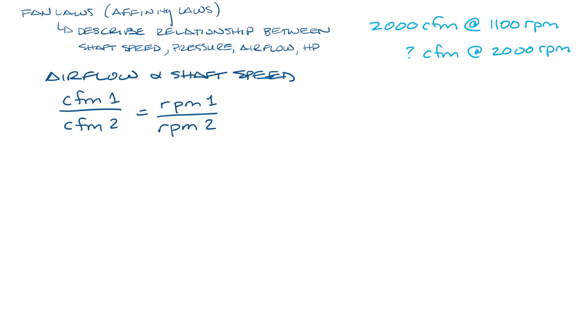Well you can use this equation to get CFM2 equals CFM1 times RPM2 divided by RPM1. And when we put our numbers in there, we get that the CFM would be about 3636 CFM.